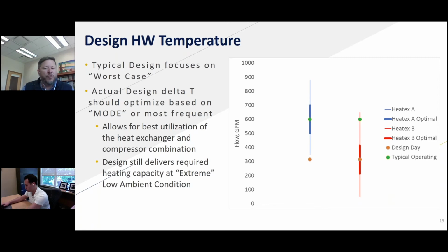And that's because our flow is so low. There's a couple of reasons for that. As we reduce the flow through the heat exchanger, you have a min and a max flow. If you get below that minimum flow, we start to see laminar flow. Obviously that affects us if we're in heating mode and transferring energy from the refrigerant to the water. If I go to laminar flow, it makes it more difficult to transfer the energy, no different than on our coil that was frosted. Also, if it's a two-pipe system, we're using the same heat exchanger for defrost. Now it's actually being used as an evaporator, and we're going to see challenges there as well if we're operating at those lower flows and going laminar again.